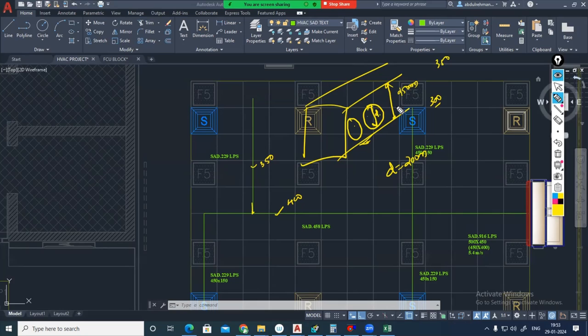Since the flexible duct diameter is 200, I have to place my flexible duct collar there. Then I have to hammer it on the top side and bottom side. That's why the height should have 25 mm on the top side and 25 mm on the bottom. The 25 mm on the right and left is not an issue because that affects the length only, and we have enough space there. Height matters. So the minimum height I need, with a flexible duct diameter of 200, is 250 mm. Now I can size that branch.